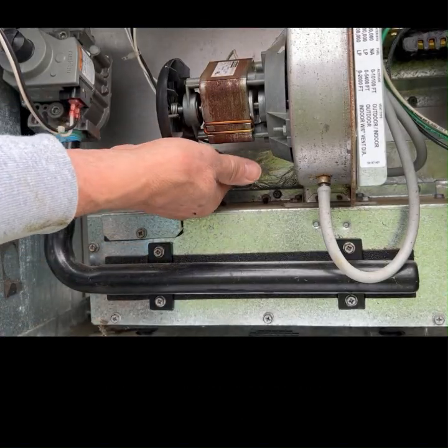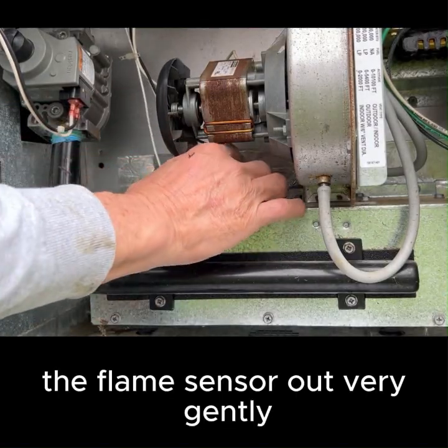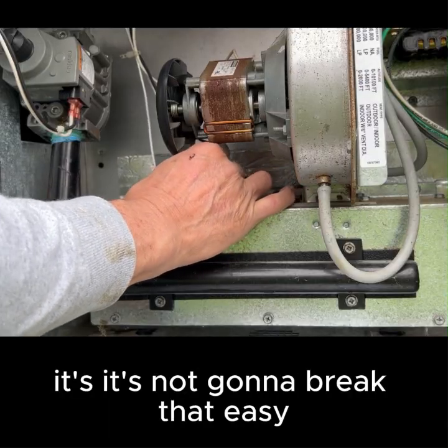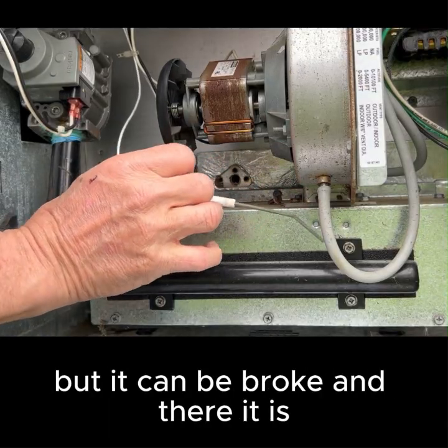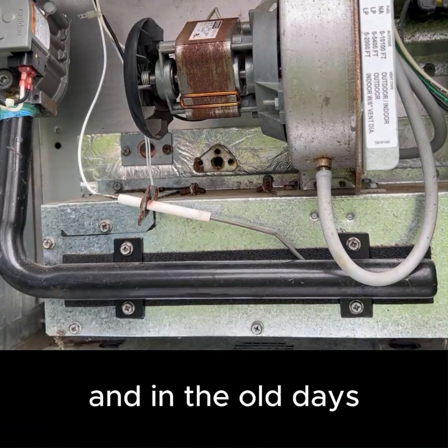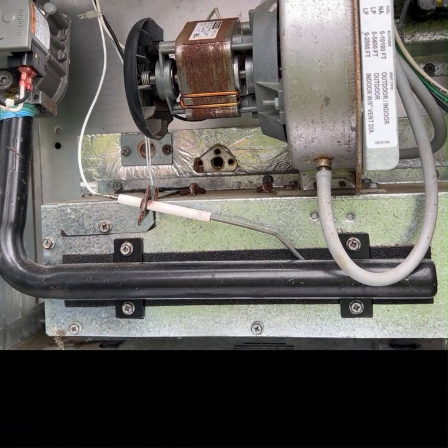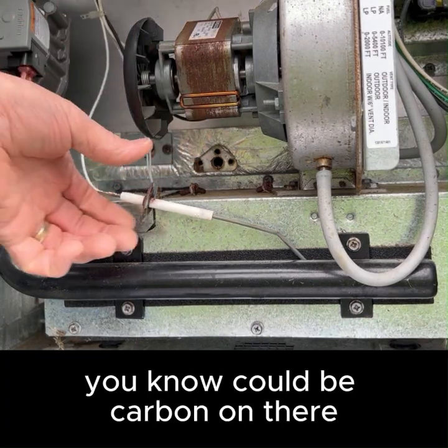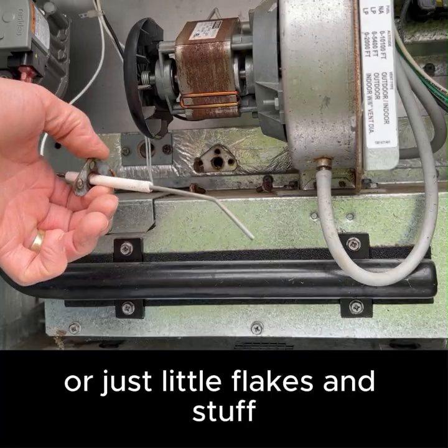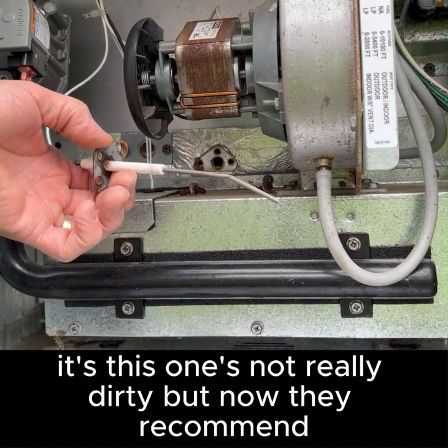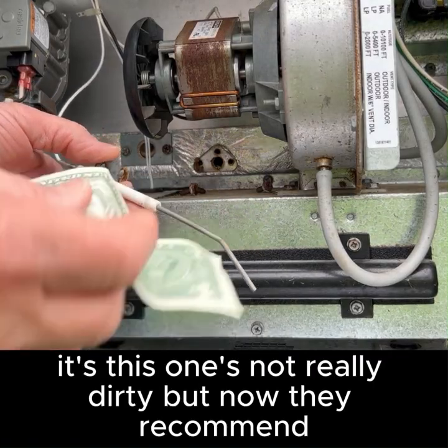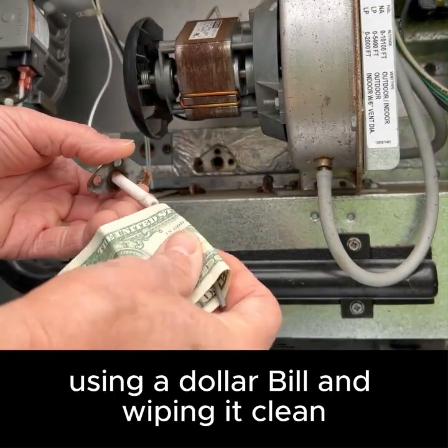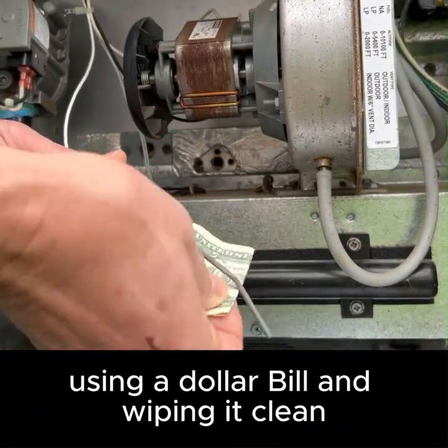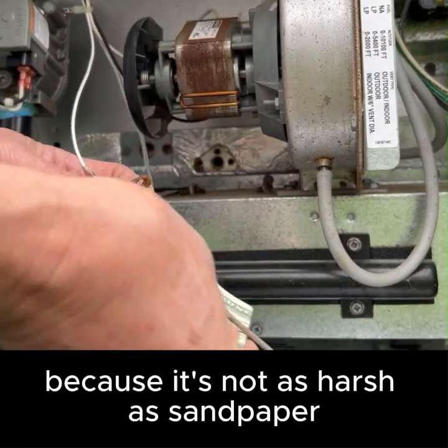And then you pull the flame sensor out very gently. It's not going to break that easy, but it can be broken. And there it is. And in the old days, we would take some real fine sand cloth and clean it off that way. There could be carbon on there or just little flakes of stuff. This one's not really dirty, but now they recommend using a dollar bill and wiping it clean because it's not as harsh as sandpaper.